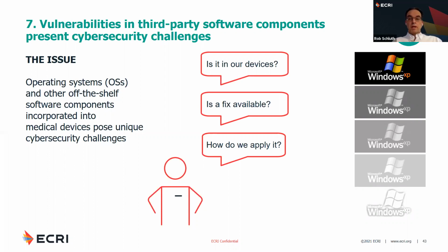Another factor that comes into play here is that some medical devices have a very long lifespan. They might be usable for 10 or 20 years, whereas some of these software components don't tend to last that long, and eventually they go out of support. So there I got an image of Windows XP from however many decades ago that was. For the longest time, medical devices might have been based off of that system. Microsoft is no longer supporting it, so those sorts of devices could maybe be at risk of malware.